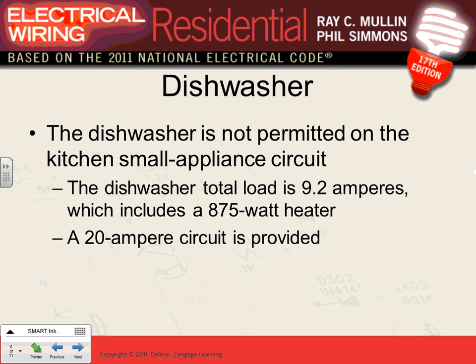With the dishwasher, the same thing. Here's my dishwasher, guys. A dishwasher is an appliance. If you do the same math on the dishwasher being an appliance, you guys remember when we highlighted for appliances, actually the garbage disposal could apply the same rule. Article 422 talks about appliances, and it says if the full load current is 13 or less for an appliance, you have to provide a 20 amp circuit for it.